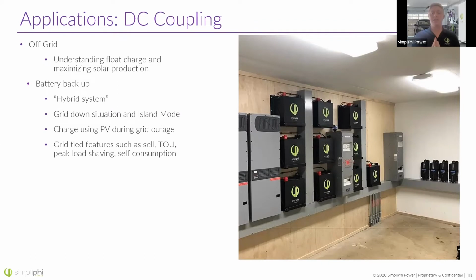So your inverter can see, okay, the grid is over here on the AC bus, the PV is over here on the DC bus. Right now, I've been programmed to use only DC power or renewable energy because it's 5 to 9 p.m. and the grid power is more expensive right now. I'm not going to use power from the AC bus. Instead, I'm going to sell power to the AC bus because time of use is advantageous to sell right now. So having DC coupled systems that are grid tied really gives you the maximum amount of control over where your power is coming from and where it's going.